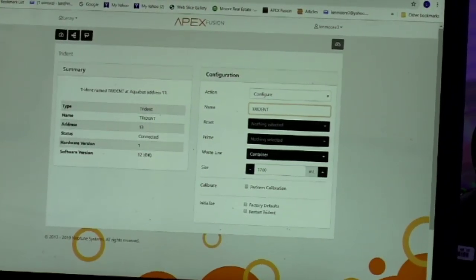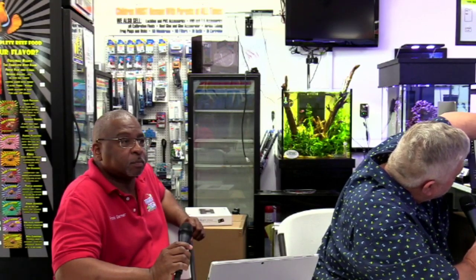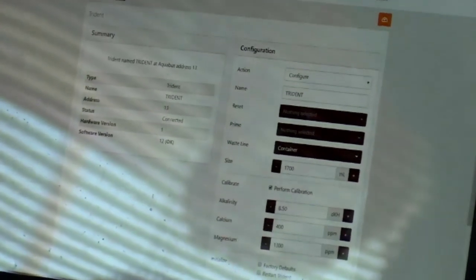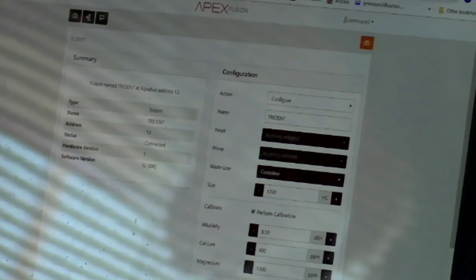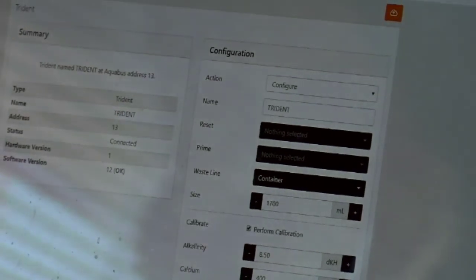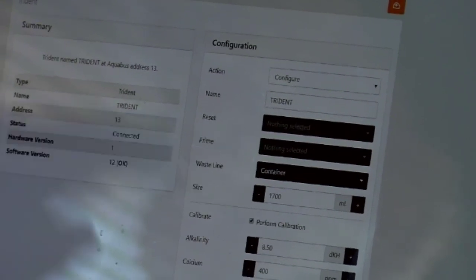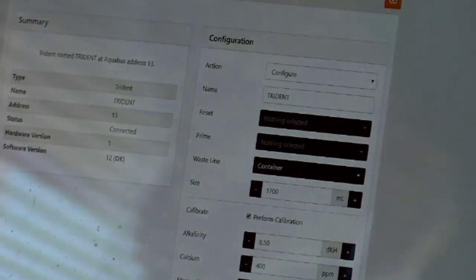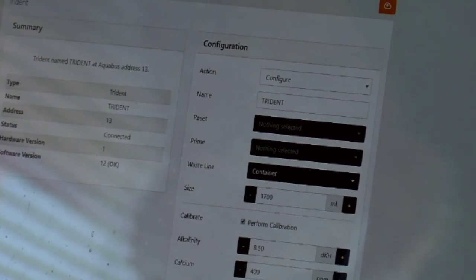And I just wanted to show you how easy the calibration is. In this business, calibration is very important, and it's always something you've got to do just to keep it calibrated. And what they've done is made it very simple. If I touch calibration here, calibrate. I take my calibration bottle that comes from Trident, set it on and put my feed tube into the bottle, and it sucks up a sample. And when the sample's done, I match the numbers here with the numbers on the bottle and hit go, and it's calibrated. So it's very simple to calibrate.